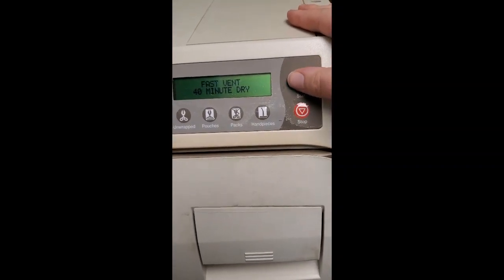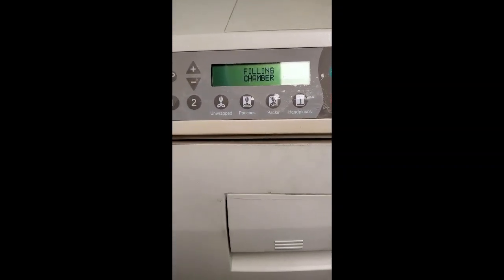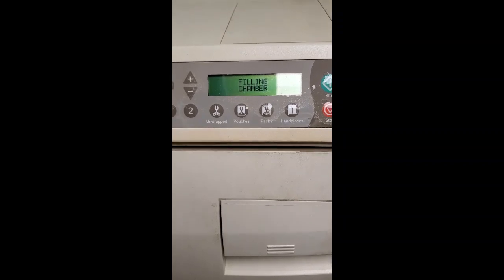And then we're just going to hit start, and the chamber is going to fill. For some autoclaves, the chamber doesn't automatically fill. You have to manually do that. So in that case, you would just watch the autoclave, watch that water entering that bottom, making sure it didn't overflow. And then when it was at the right level, you would stop it from filling, and then you would close it and start your cycle. We're going to take a pause right here, and we'll be back when the autoclave is ready to vent.